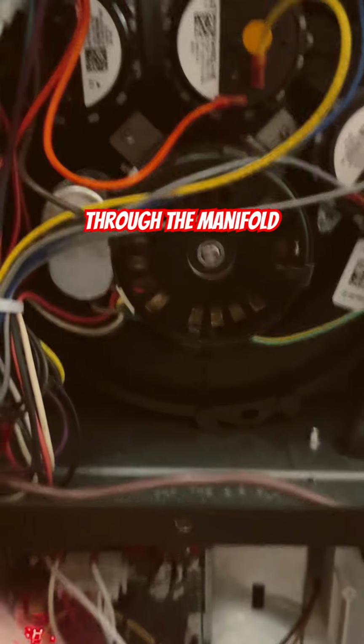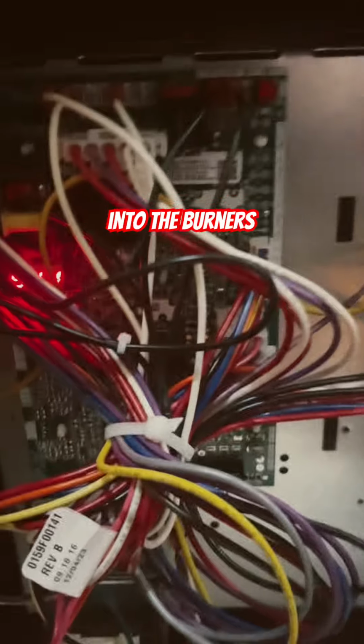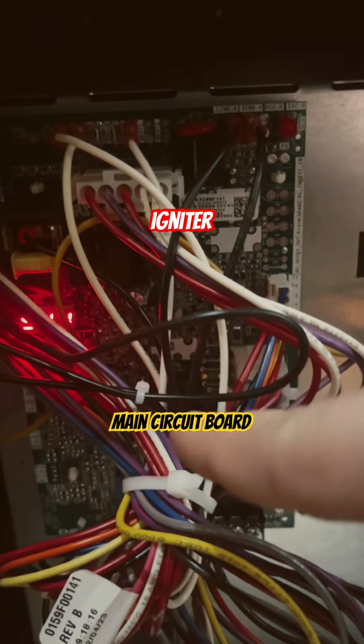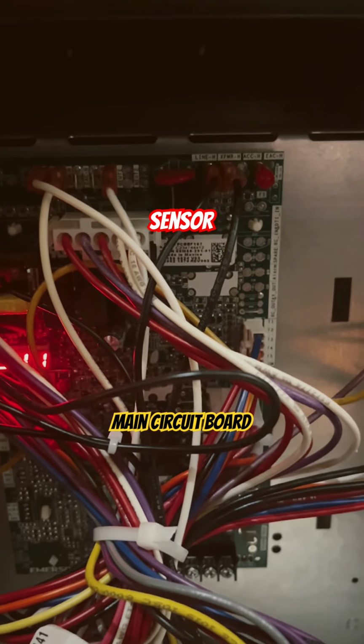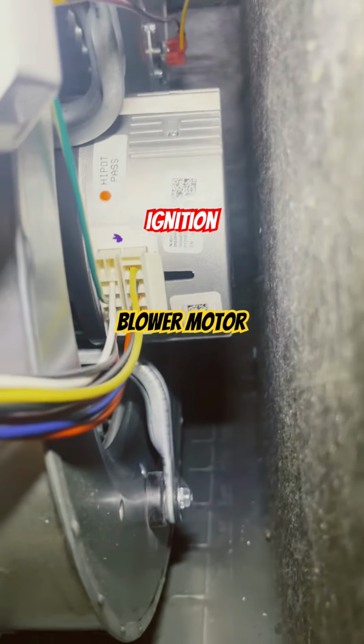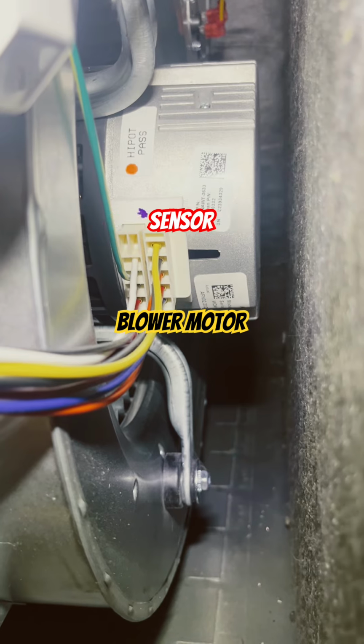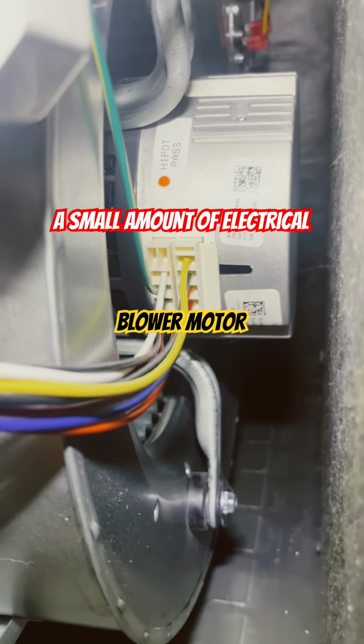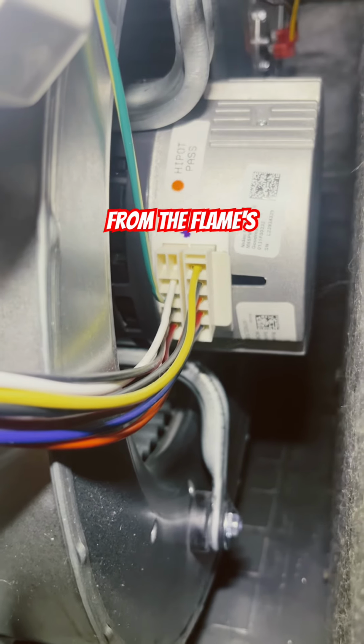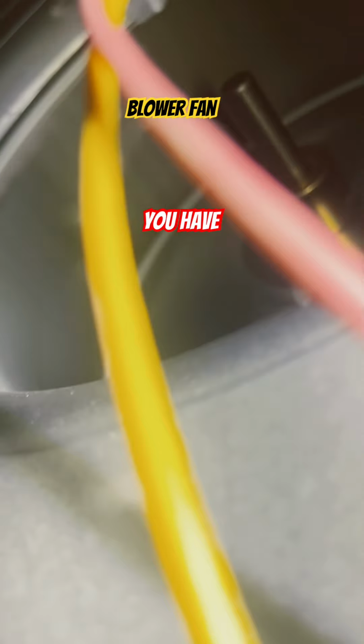This will release gas through the manifold and into the burners where it will ignite on the hot surface igniter. There's what's called a flame sensor that, well, senses a flame. This is a safety feature that prevents backfires and delayed ignition. Once there is consistent flame on the flame sensor for long enough, it will create a small amount of electrical energy from the flame's thermal energy in a process which is called either flame ionization or flame rectification, depending on what type of system you have.